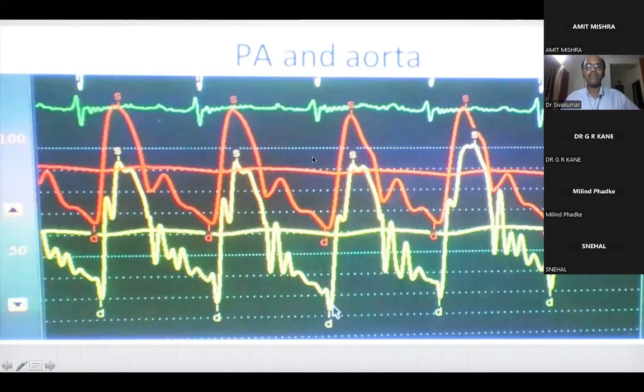Now, automatically every machine will generate a systolic and a diastolic if you are putting in an arterial mode. So in this particular trace, the machine will give a systolic value of somewhere around 95 and a diastolic value of somewhere around 25. But the truth is the PA diastolic is actually stopping here. And this is because of the underdamping. So one of the most important things you should follow when interpreting a pressure trace is you yourself have to go and look at this trace rather than finding out what the machine records as systolic and diastolic and then copying it onto your report.